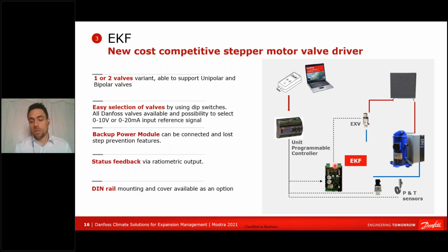So that solution allows you to have different kinds of design. You don't have to get the superheat controller and use it as a standalone; you can just use it as a driver. With the EKF, you can start to imagine everything you can do with a driven valve. It could be main expansion, gas bypass, defrost, anything, even a staging valve for a turbo chiller. You can drive that with the EKF.